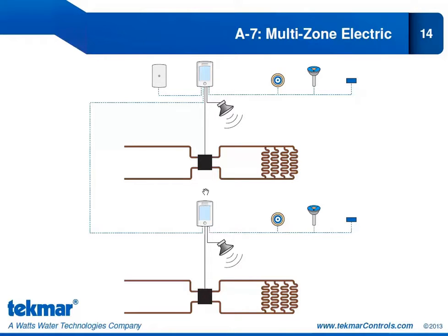Because this is not a hydronic system, we are able to use the auxiliary relay to operate some alert equipment. So we would connect to a third-party alert device, which could either give an audible alarm or perhaps even trigger an email that could be sent to a smartphone so that we can be notified of any issues immediately in our system. You'll notice we are connected to one outdoor sensor, and that outdoor temperature will be communicated to any other 654s on our system through the tekmarNet communication.